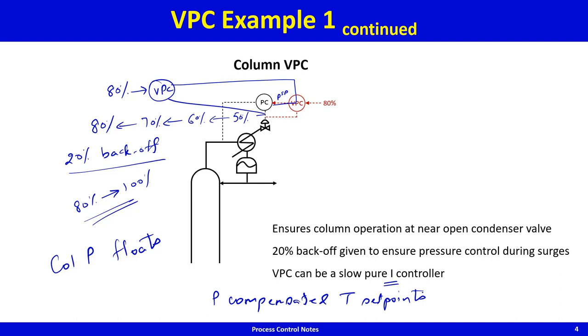Composition is indirectly controlled by holding temperature, because temperature is so much easier to measure. But the assumption is that pressure is constant. Now that column pressure is floating, holding temperature constant doesn't tell you whether the temperature change is due to composition change or pressure change. Therefore, if you still want to use temperature control, you will have to compensate the temperature set point for changes in column pressure.